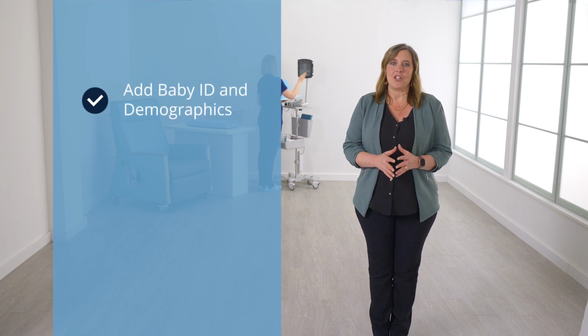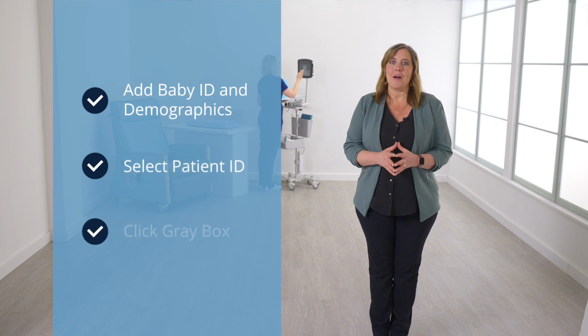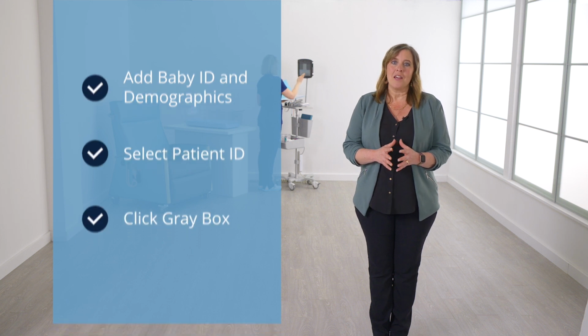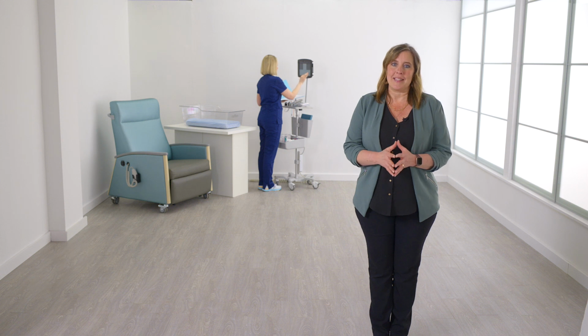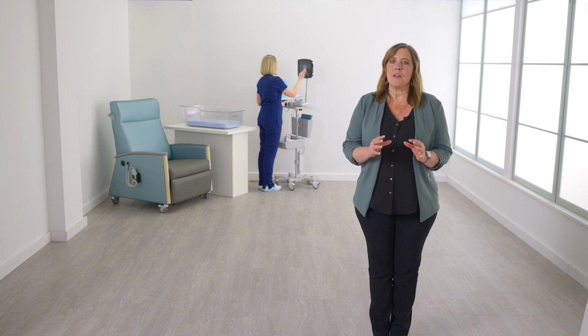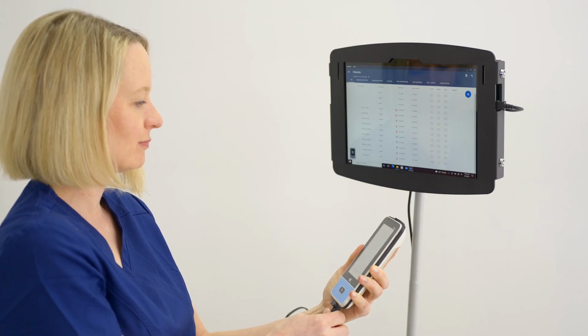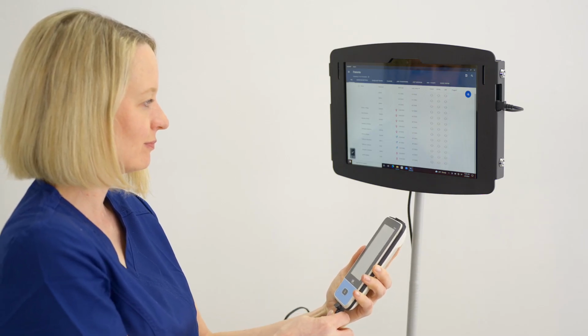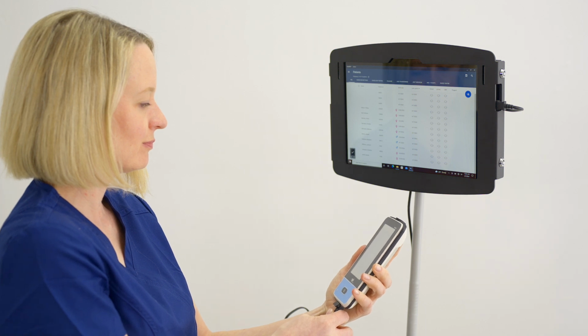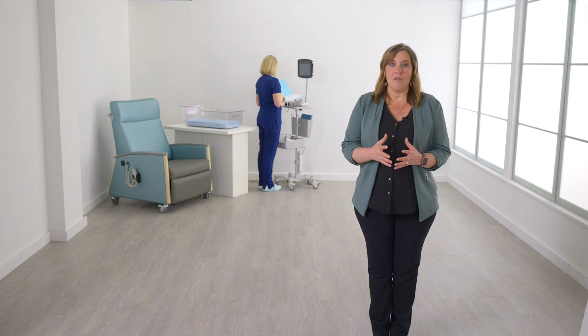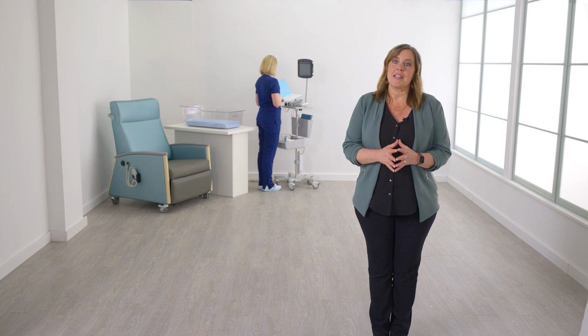To create a patient list, add each baby ID and any additional demographics to HearSIM. Select the patient ID and click in the gray box that appears on the name column. Complete this step for all babies to be tested that day, including babies that may need rescreening. Once the list is complete, connect the Novus to the computer, click on the animated icon, and select Transfer. Once screening has been completed for the day, connect the Novus, click on the animated icon, and select Import. All test results will be transferred into HearSIM and deleted from the Novus.